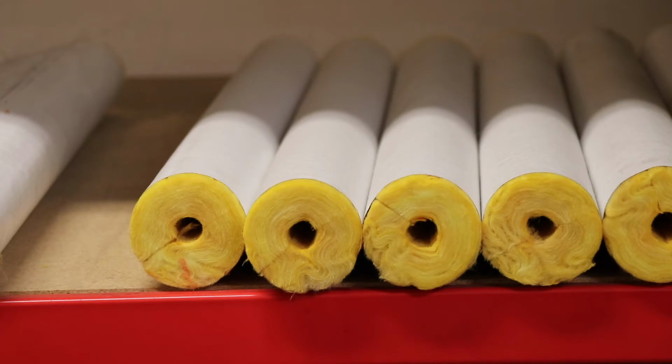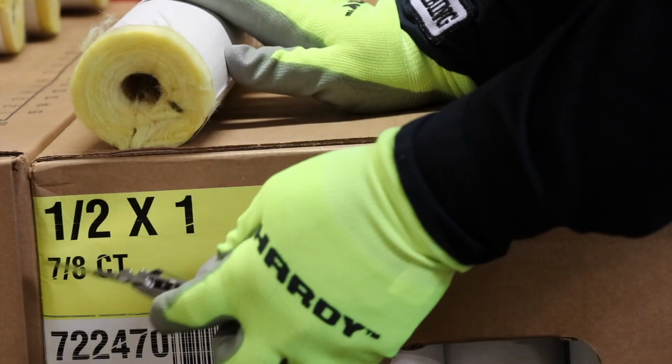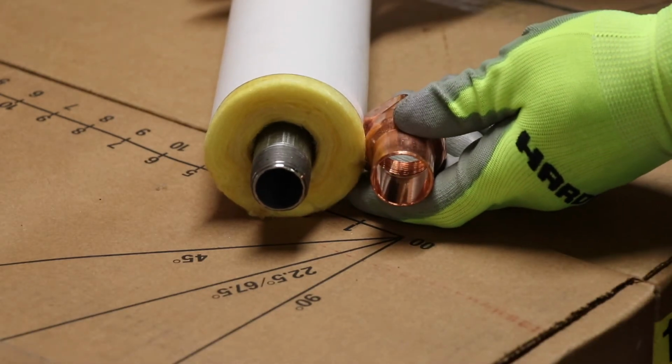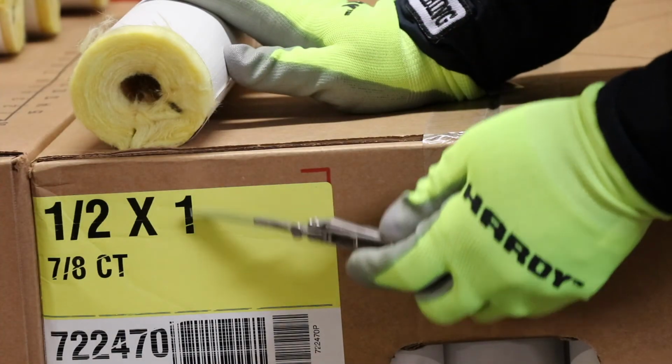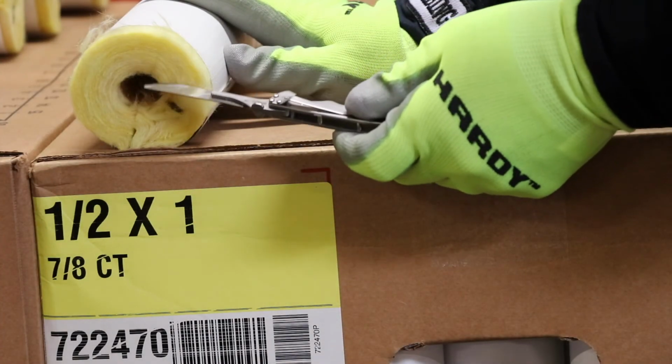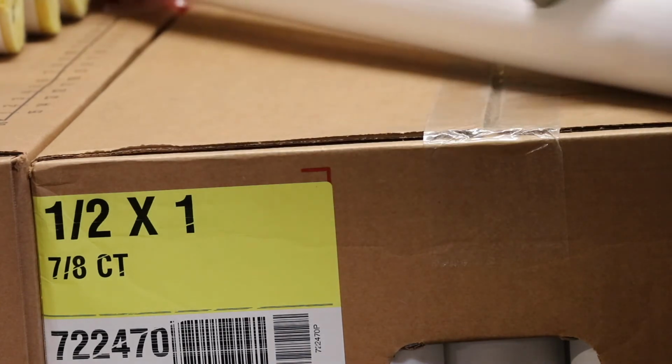Moving on to fiberglass insulation. Same principles apply here. Are you ready for this? It's used as an insulation around pipe. Now fiberglass is dual sized, meaning you can see here it's for 1/2 inch iron pipe or 7/8 copper tube size, so 3/4 copper tube. And then of course you can see the one number is a 1 inch wall thickness. I believe we only carry it in 1 inch wall.